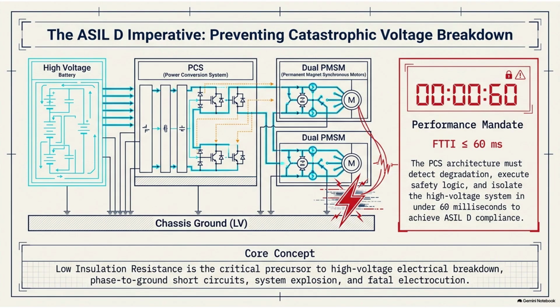Exactly. Now apply that to an EV motor. These incredibly fast switching speeds create high voltage reflection waves. You basically have electrical pressure waves slamming into the first few turns of the copper wire inside the motor. And if that electrical pressure is too high for the plastic insulation wrapping those wires, what happens?